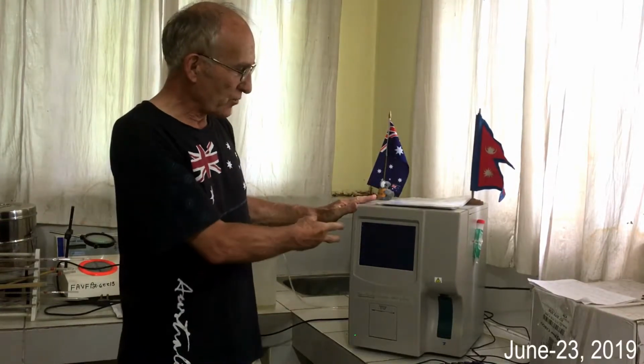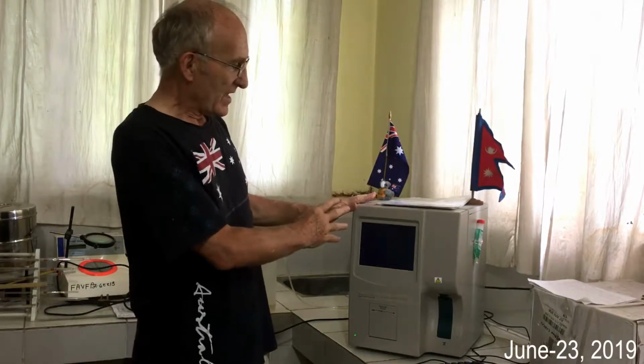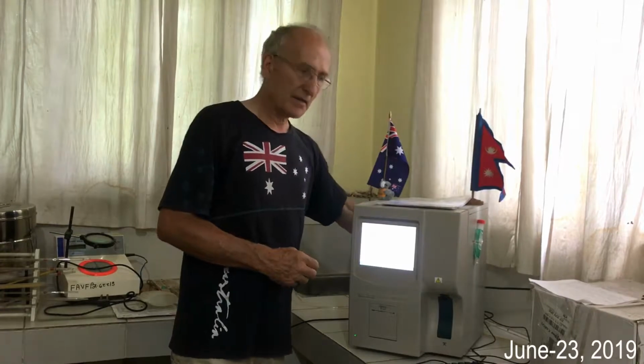While the machine is powering up, I'll talk a little bit more about the machine. We have the main component here, which is warming up. This is the computer. Information is fed into this via the keyboard using the mouse. And the machine itself uses reagents. Now the reagents are stored in these boxes. There are three boxes, two larger ones at the side, one smaller box at the back. The machine sucks up the reagents through these tubes, and the reagents, after they've been used, go into this waste container.